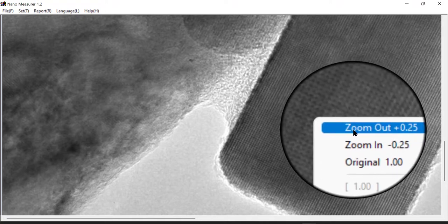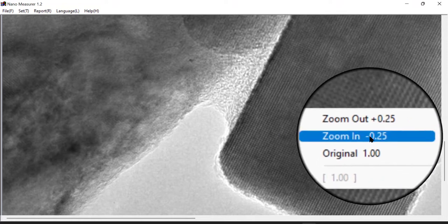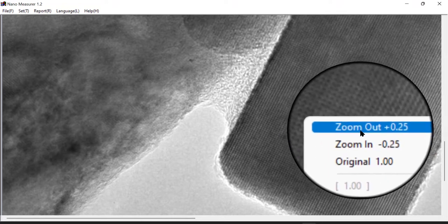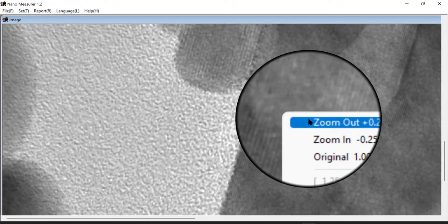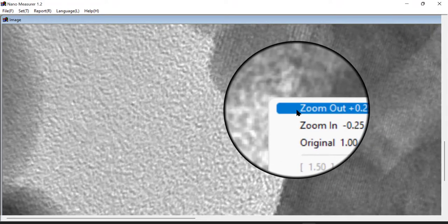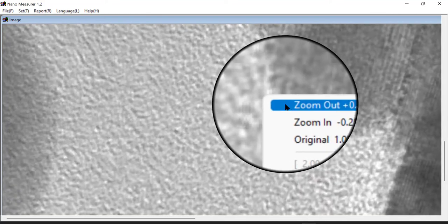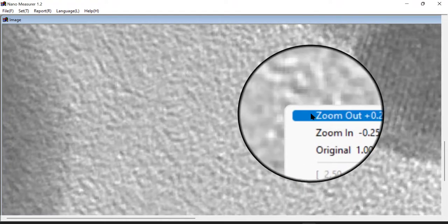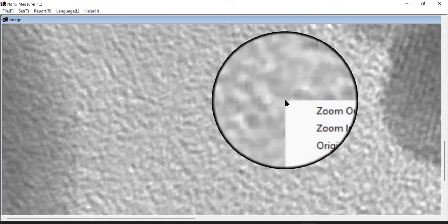Now, suppose this is the rod where we want to focus and measure the D value, you can right click, and here there are three options: zoom out, zoom in, or original. So if you click on zoom out, it will start to zoom. Okay, so at each click you can zoom plus 0.25. So you can first go to the maximum. So I think it may reach in 9 or 10 clicks.